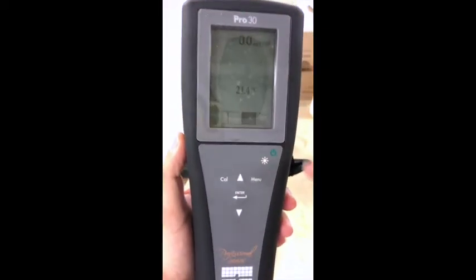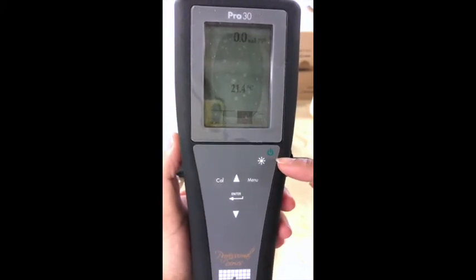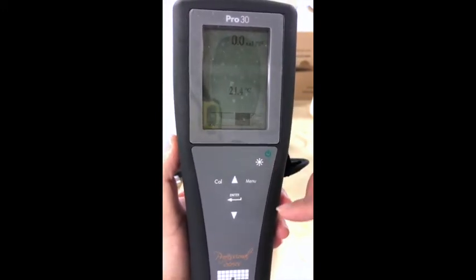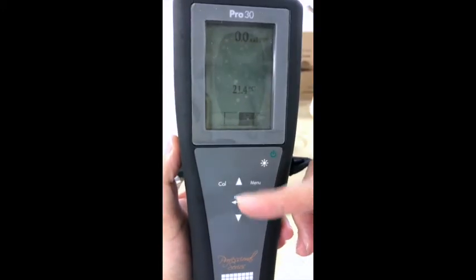As you can see, the SAL and the unit PPT. PPT means parts per thousand. It means that 1 kilogram of water sample contains 1 gram of dissolved salt. Same as the pH measurement, it will measure the temperature of the sample also. When we want to use the conductivity meter, just press the on and off button.